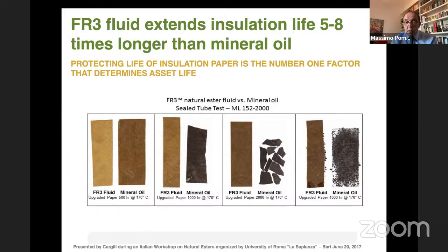The third box is 2,000 hours. You can see the difference. The papers really, in the case of mineral oil, did break, meaning it's no longer consistent. And the last one, the paper is completely destroyed by the oil. This happens only for mineral oil, not for natural ester liquid.